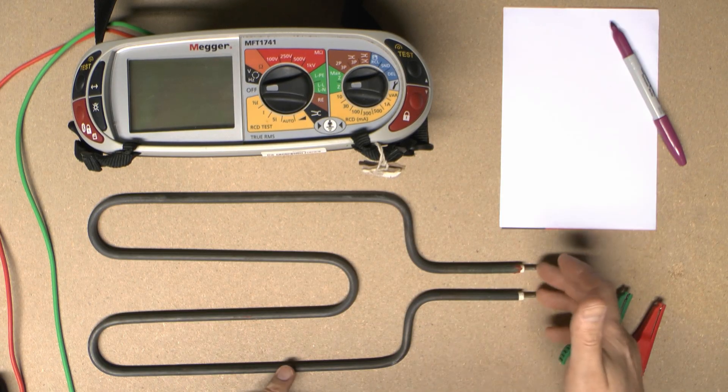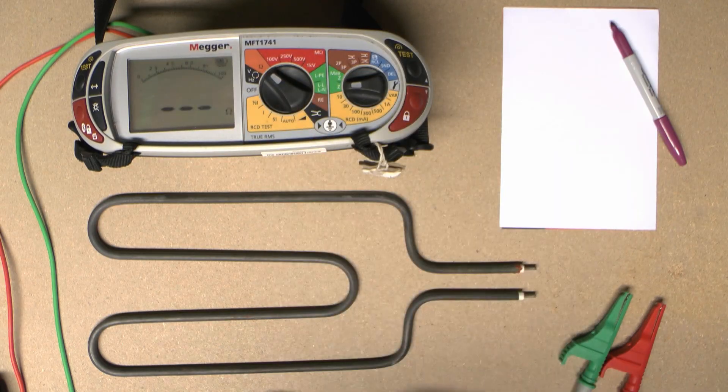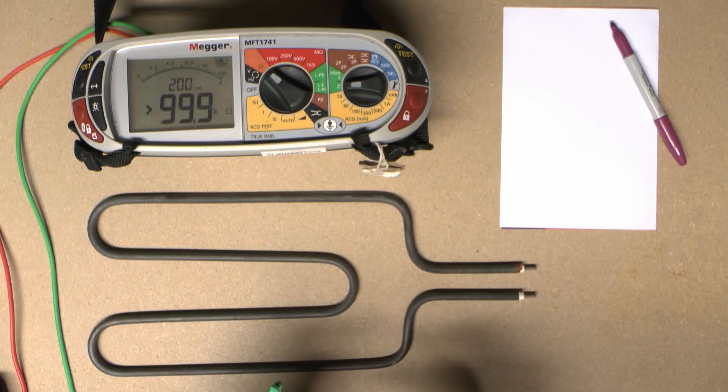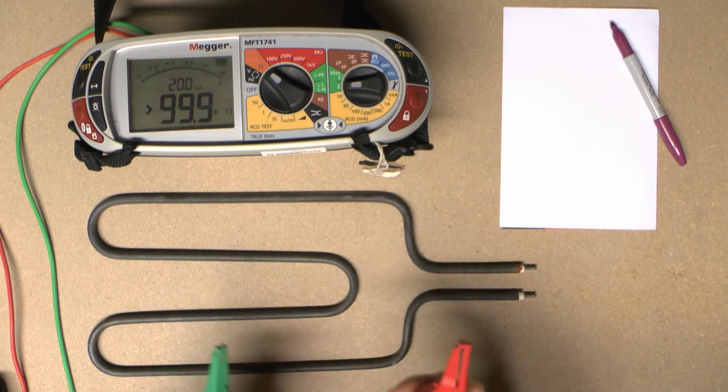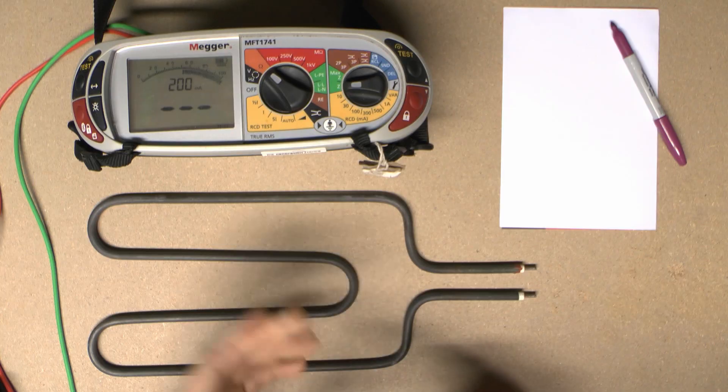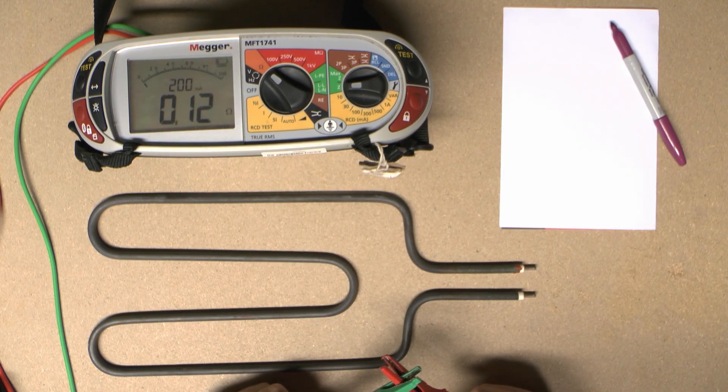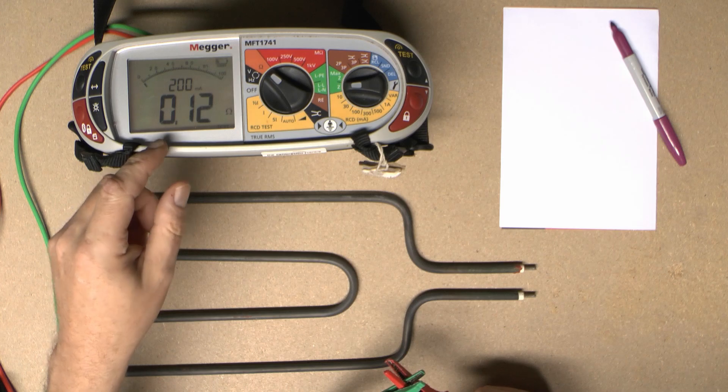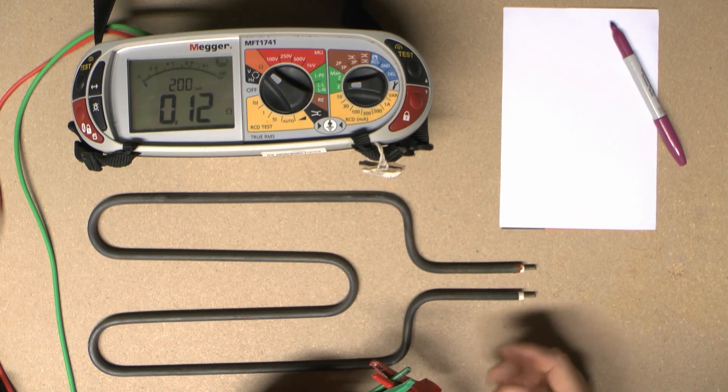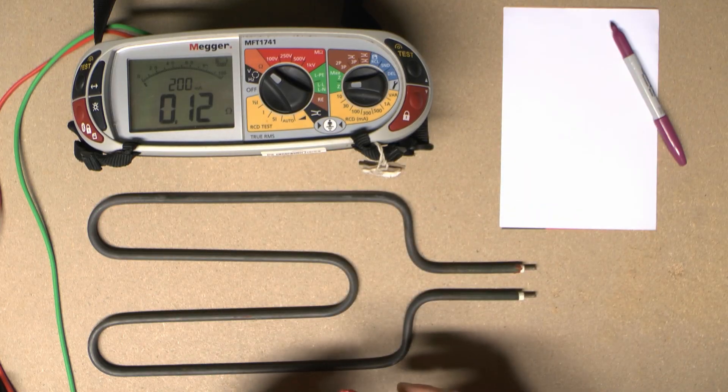For the first test, we're going to check resistance. Select resistance or ohms on whatever device you've got. It's a good idea to check between the two leads before testing to make sure they're connected correctly and not broken. If we connect those together, we should get pretty much zero, 0.12 ohms in this case. You can zero that out, and you would normally do that when testing a circuit. But with an element, because the resistance is large compared to that tiny amount, it doesn't particularly matter.